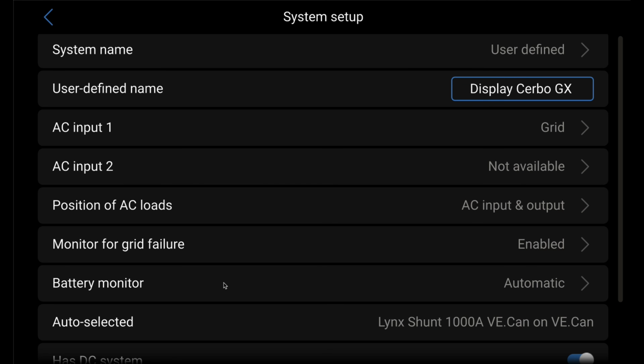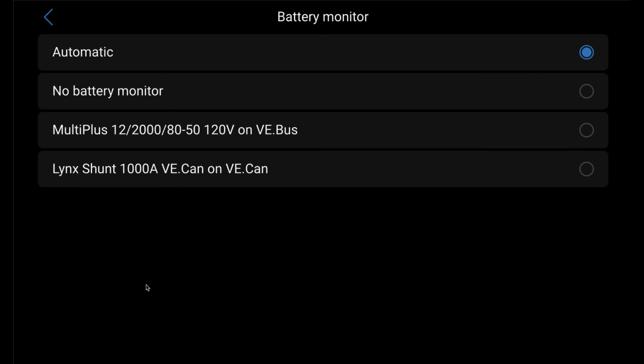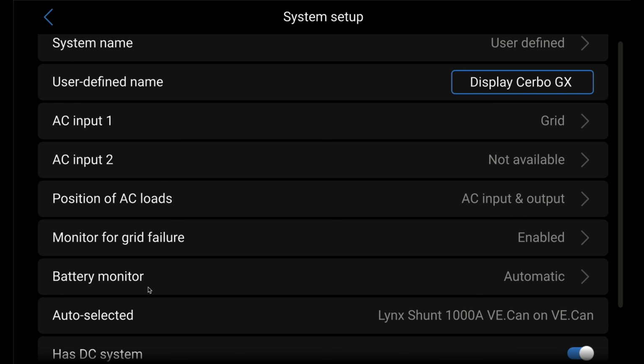We also have the ability to adjust our battery monitor selection. If you have more than one device in the system that can display state of charge, you can set it manually based on preference. By default it's set to automatic, and typically that's fine, but in large systems with multiple shunts, you can manually select which device provides that data. Because we have it set to automatic, it shows the currently selected device, in our case a Lynx shunt.